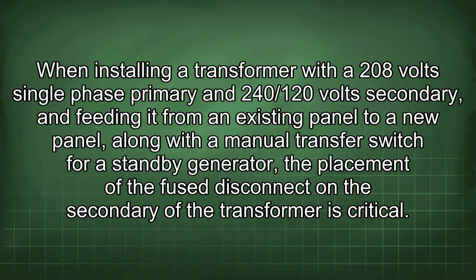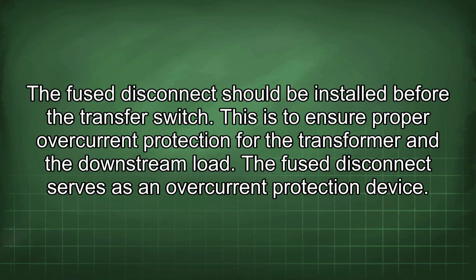When installing a transformer with a 208-volt single-phase primary and 240/120-volt secondary, and feeding it from an existing panel to a new panel, along with a manual transfer switch for a standby generator, the placement of the fused disconnect on the secondary of the transformer is critical. The fused disconnect should be installed before the transfer switch. This is to ensure proper overcurrent protection for the transformer and the downstream load.